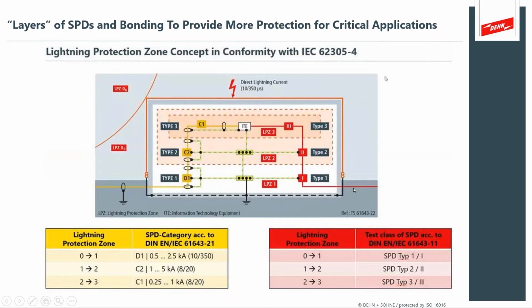The application of surge protection devices and the application of grounding and bonding measures lets you build a more and more controlled lightning protection zone. So something that might be an exposed power line coming into the building might be considered a type 1, and then where that particular power line or data control line comes into the final control room would be considered your more sensitive lightning protection zone. So it's a way of applying protection measures to create layers of protection so that you're more robust. And in this diagram, you can see all your pillars of protection.